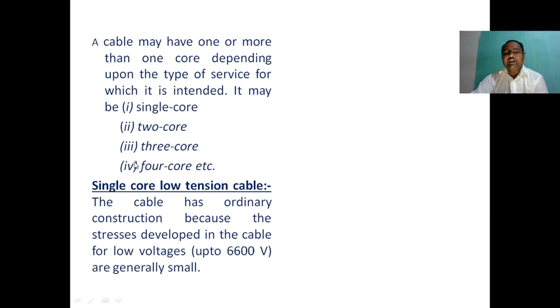Please see the diagram for the single core. If you observe the diagram carefully, this is a single core low tension cable. It has only one conductor, a stranded copper conductor. We use copper as the conductor. Then there is impregnated paper, lead sheath, and serving. In between the conductor and the lead sheath, there is impregnated paper. These cables handle only 6600 volts, which is 6.6 kV.